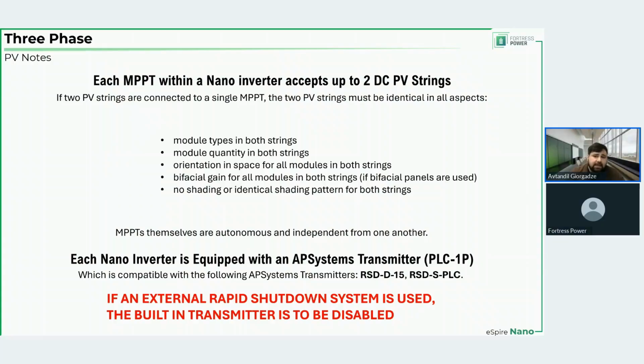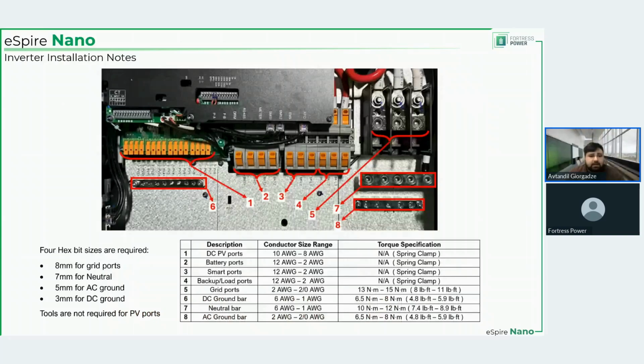So with that out of the way, you notice here that for the grid ports, for the neutral and ground bars, there are screws, but for DC coupled PV, for battery, for backup load output, for smart ports, there are no screws. That's because you don't need screwdrivers and screws to use these. These are like spring lock mechanisms that latch onto the cable, and you don't necessarily need a screwdriver to screw something in place. For DC coupled PV, no tool whatsoever is needed. You can use your fingers.